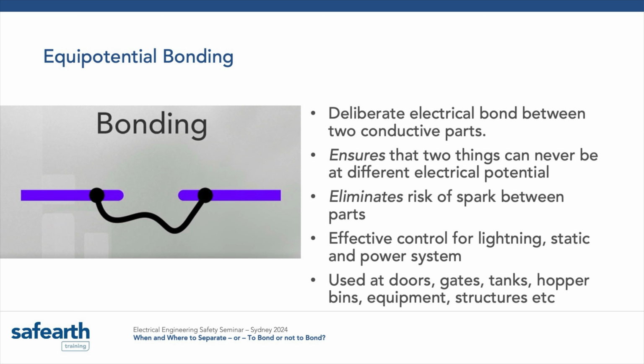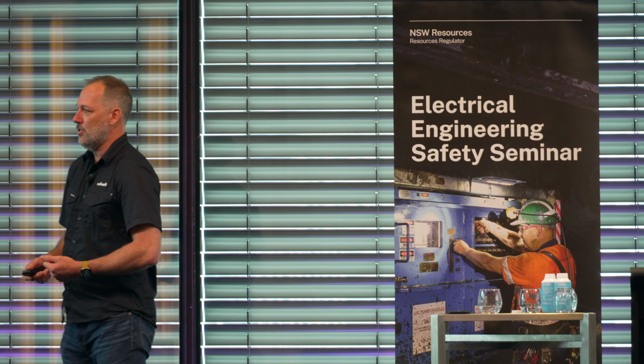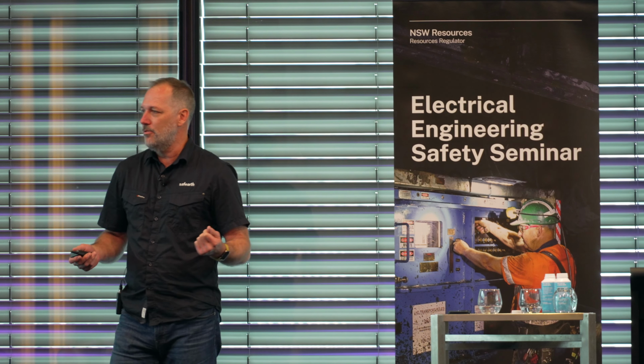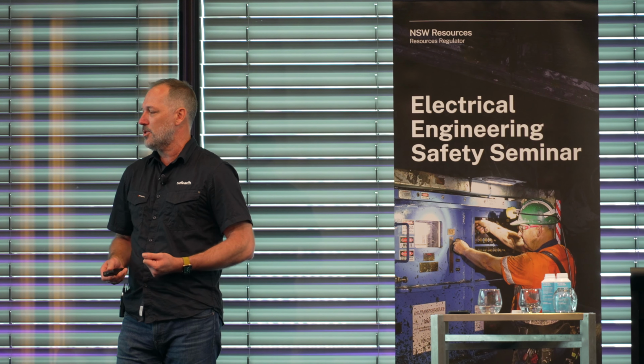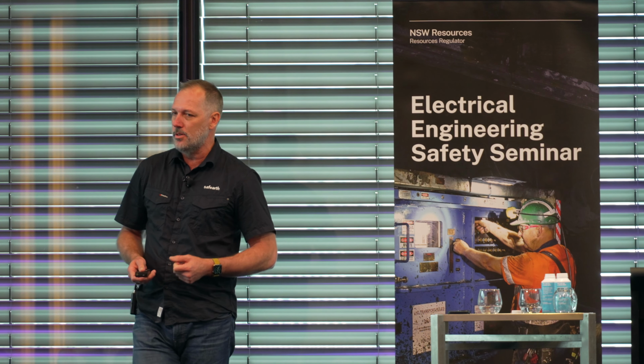It eliminates the risk of spark between parts. Again, I wouldn't necessarily say that's entirely true, because it depends on how well the connection is made. You could introduce a spark. Once you bring things too close together, if you put a lug onto a painted surface and you don't prepare it properly, well, then you've probably created all the mechanisms for a spark to initiate with a high enough voltage to break down that insulation of the paint, as an example. So I suppose bonding, it's a simple concept, but you can get things wrong.